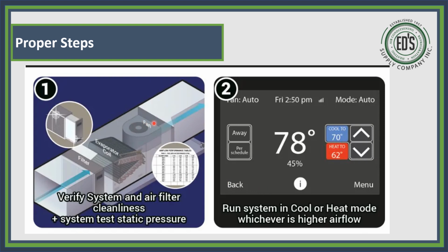So here's our furnace. There's our blower motor. Here's our evaporator coil. And we've got a filter here. So this one is a different system. You're coming in through the return, and it's pulling air across that coil instead of blowing it through it. So we want to run the system in cool or heat mode, whichever has higher airflow. On an ICP, you need to really look at this because they will come from the factory with an AC tap usually on 2, and your heat tap will be on 4. Now, with an ICP air handler, an FEM4 or an FJMA, the 3 and 4 taps are the same RPM. 2 is medium, 3 is high, and then 5 is for a high static condition.